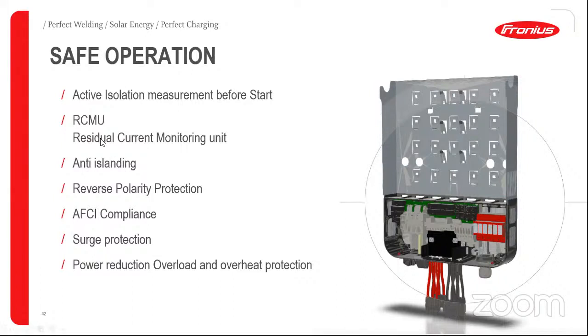Same as the RCMU. Long time ago, like 10 years ago, the inverter had a transformer inside. Now all is electronic, but with the transformer, we had a separation between the different sides. Now this is done with this RCMU unit. And when we have inverse current coming, the inverter protects itself and cuts the operation. So it also protects all the installations.